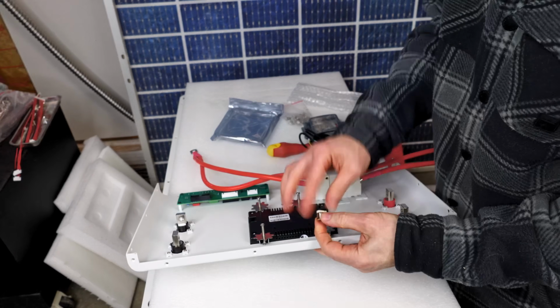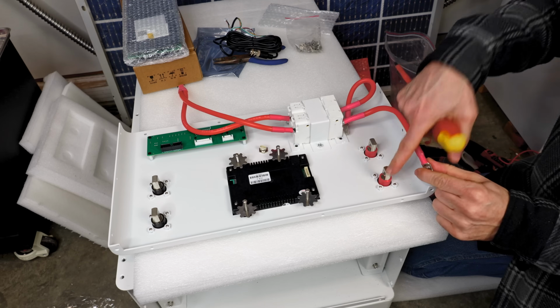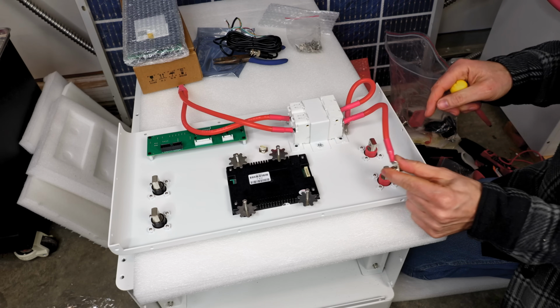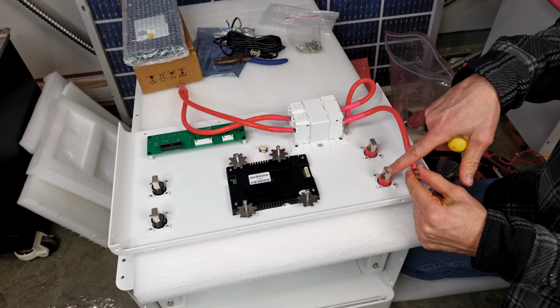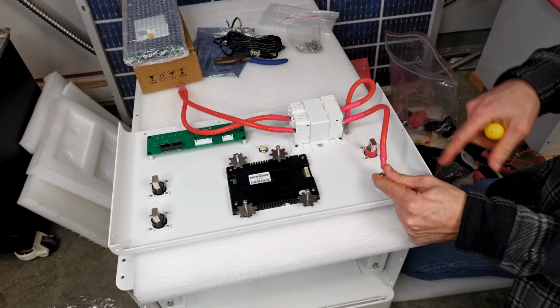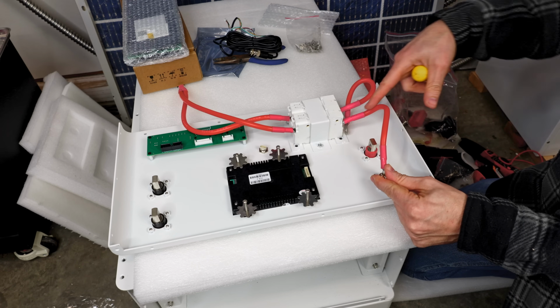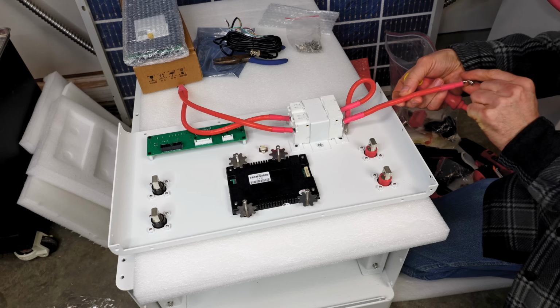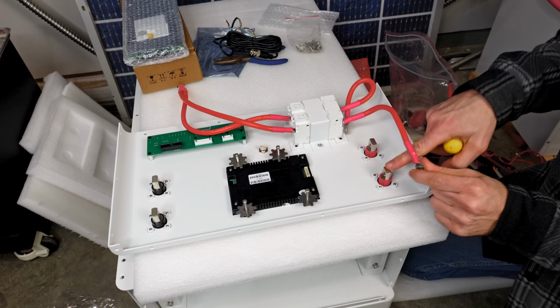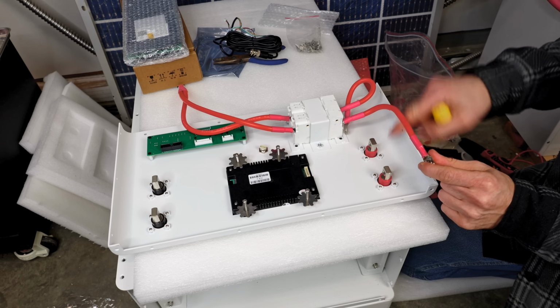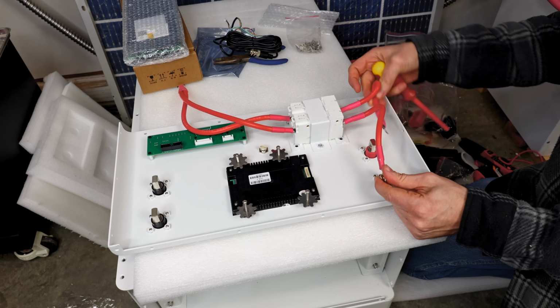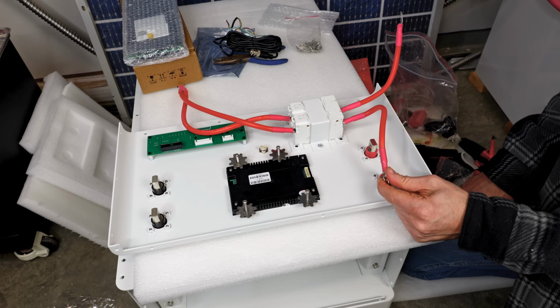This is supposed to apply one of these conductors to each of these posts. The problem is, if I connect my power out from the battery to this post, then 100% of the current has to flow through this tiny 6-gauge wire. There's no bus bar connecting these two posts, so this other conductor is completely out of the circuit.